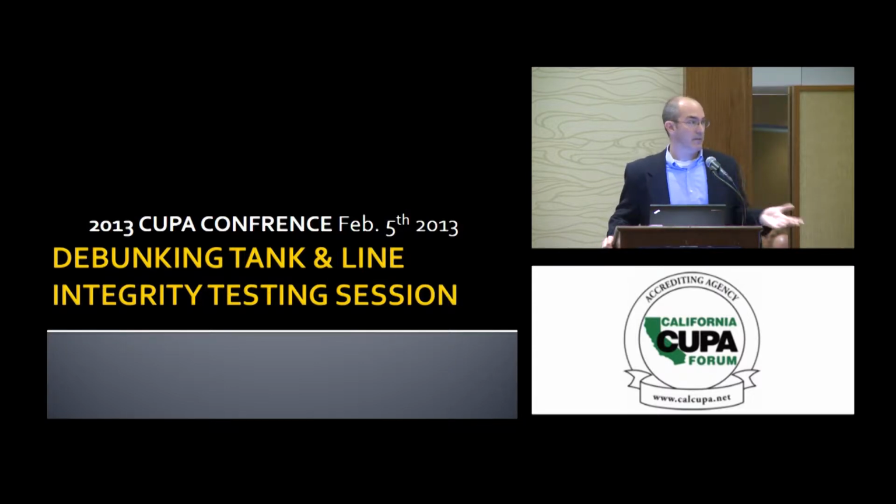With the Sure Test, you saw an example of the graphs. The trained and certified technician will evaluate those for the best and the most stable portion of that graph. Usually in the first couple of hours of any test, there's some equalization occurring, and it may take a while until it stabilizes enough. The ATGs use a proprietary algorithm to calculate a leak rate.